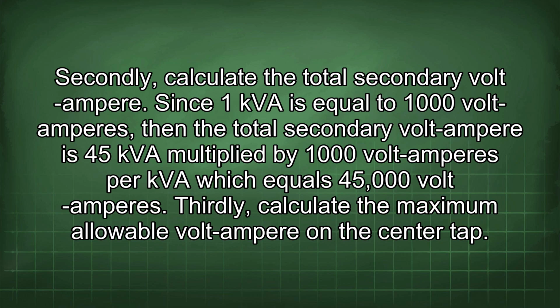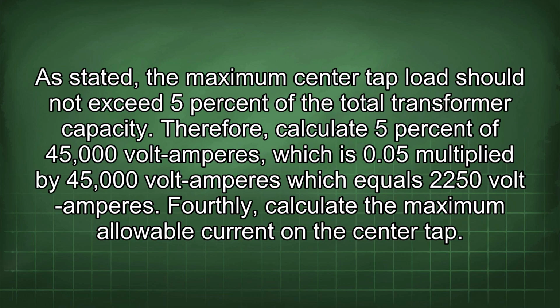Thirdly, calculate the maximum allowable volt-ampere on the center tap. As stated, the maximum center tap load should not exceed 5% of the total transformer capacity. Therefore, calculate 5% of 45,000 volt-amperes, which is 0.05 multiplied by 45,000 volt-amperes, which equals 2250 volt-amperes. Fourthly, calculate the maximum allowable current on the center tap.